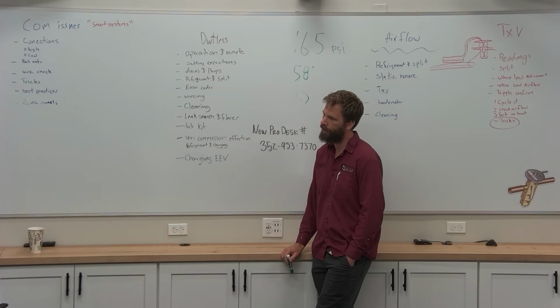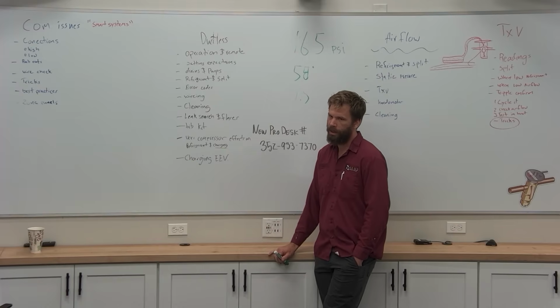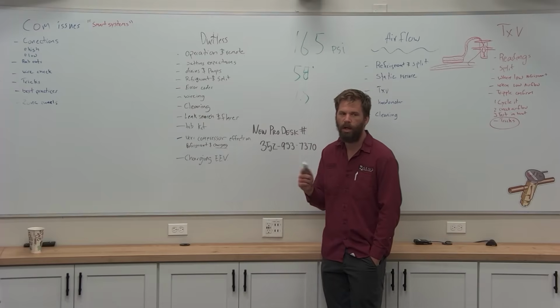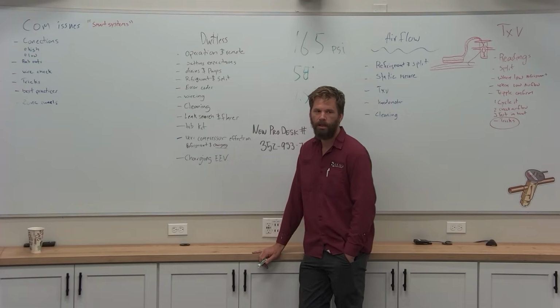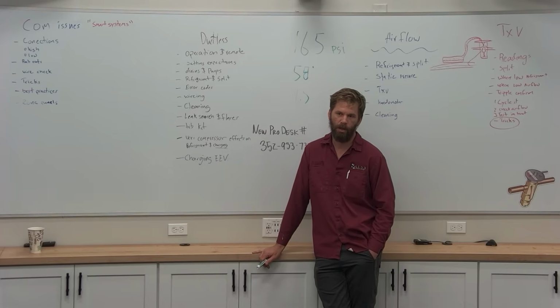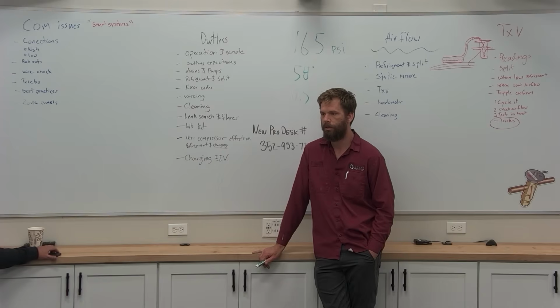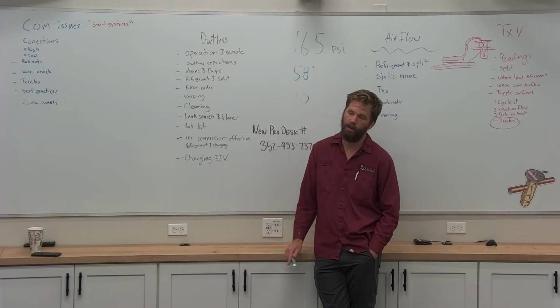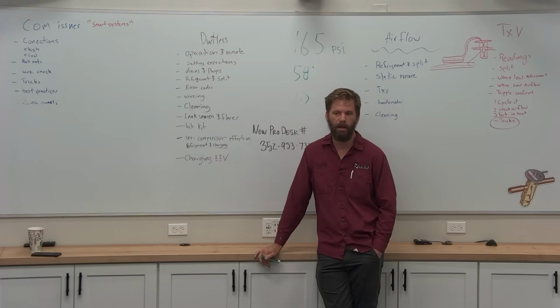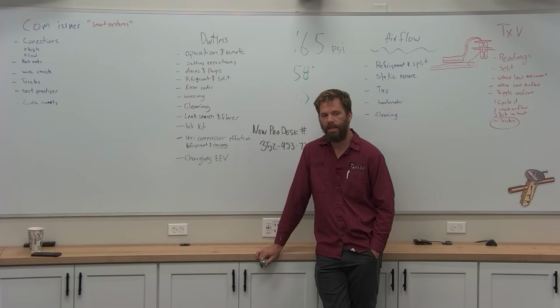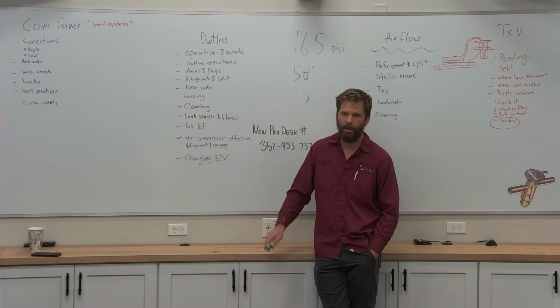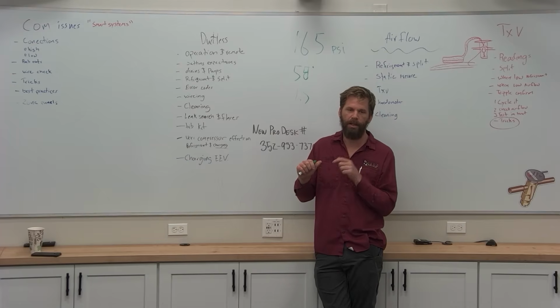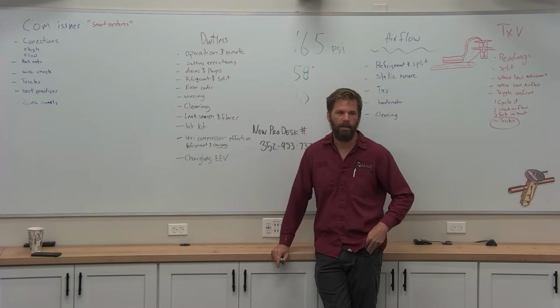The wiring? Yeah. The pro tip there is that if you're in a situation where you think, or tech support thinks, it's the communication wire between inside and outside, you can usually take a wire from your truck and connect communication and see if it happens, or you can take your meter out and ohm the connections, making sure with power off that we don't have bleed between one wire and the other. And then comparing voltage inside and outside. What voltage do I have outside, come inside, do I have the same inside? Okay, then it's probably not my wires.